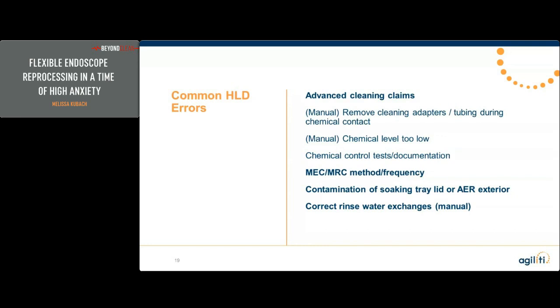Contamination of the soaking tray lid or the AER exterior. Luckily, there is not a whole lot of manual disinfection going on for flexible endoscopes anymore, and I know that this is going to be completely discouraged once again in the new ST91 that's due out this fall. But I still see occasionally someone soaking, or someone going into one of their older AERs that doesn't have a touchless system. They will load their endoscope in, they are contaminated, and then they will pull down their lid, they will touch on their keypads, or they will put the soaking tray lid back on, and some may wipe and some may not. So the next person who comes in to potentially take that endoscope out and touches those same areas and then picks up the scope is going to recontaminate their scope.